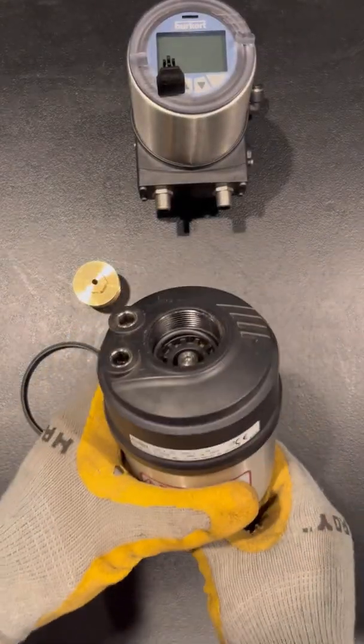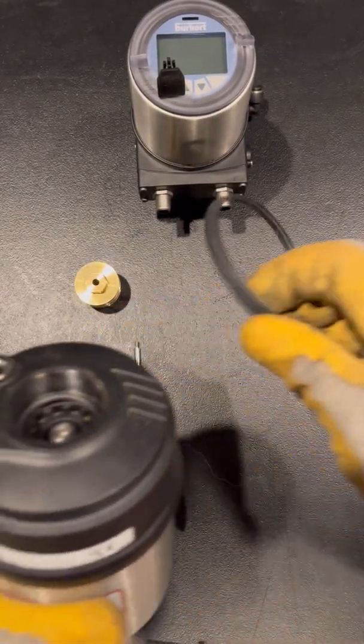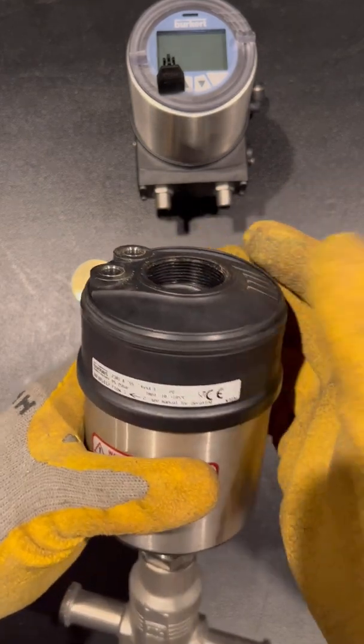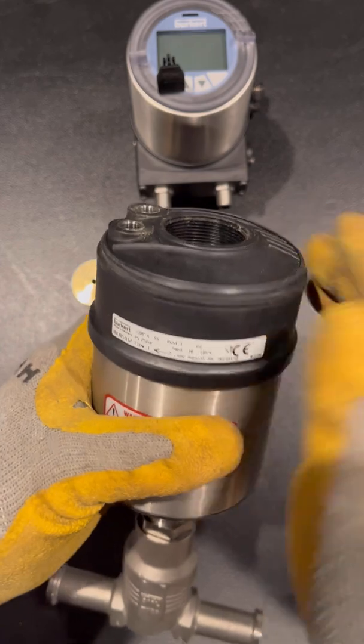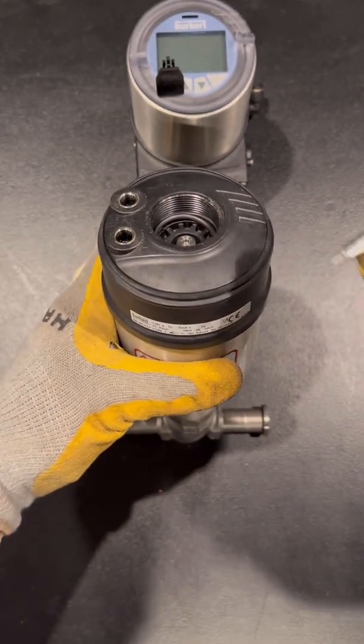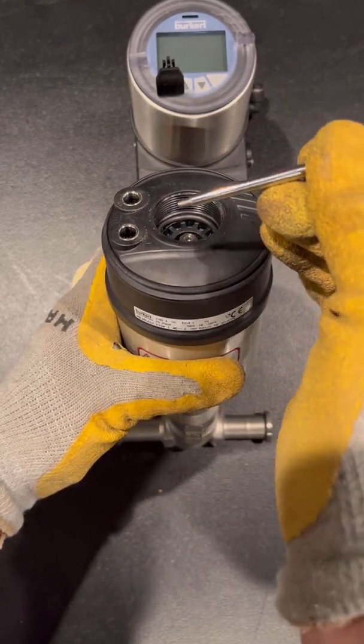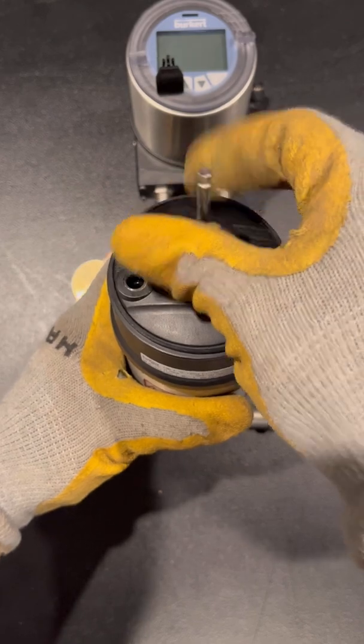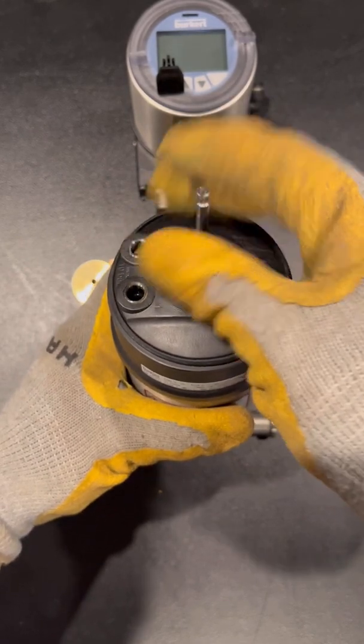Let's begin by placing the form seal on top of the Burkert element valve with the tapered side facing up. Next install the spindle onto the valve. To secure this connection apply a small amount of Loctite onto the female threaded connection located inside of the valve and then hand tighten.